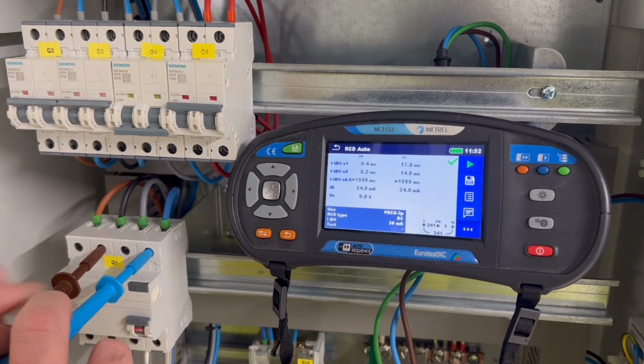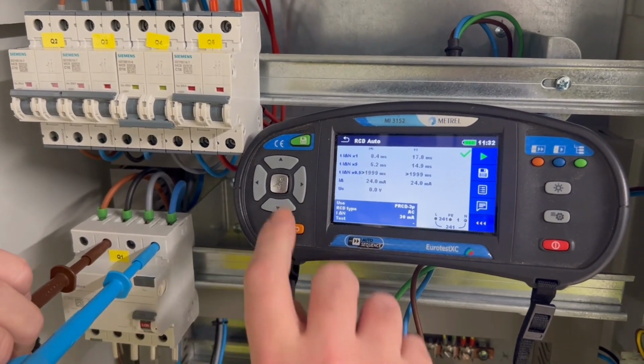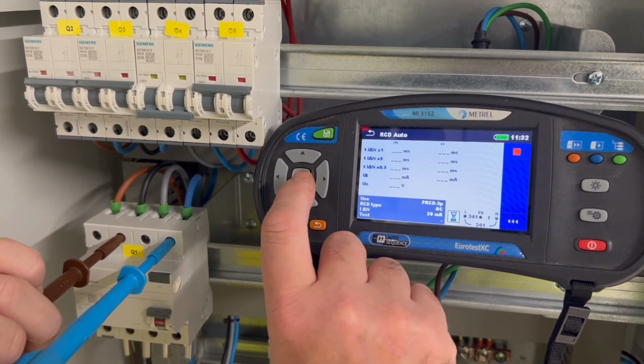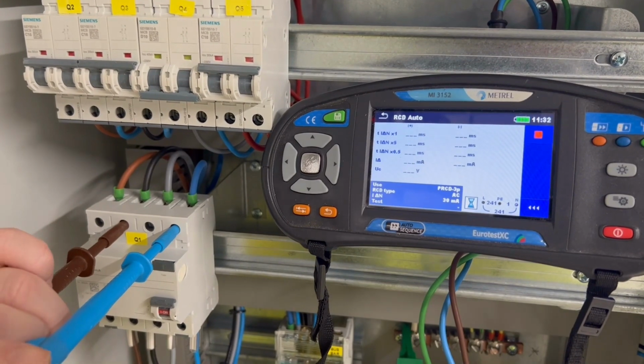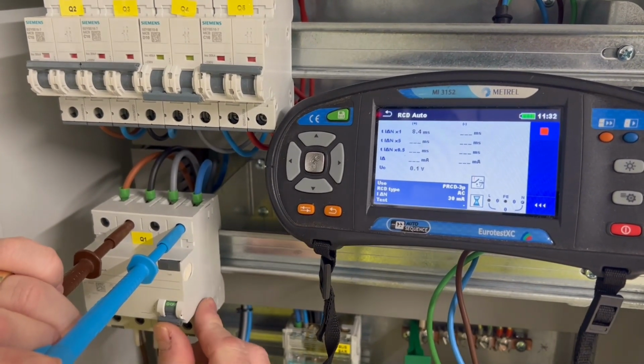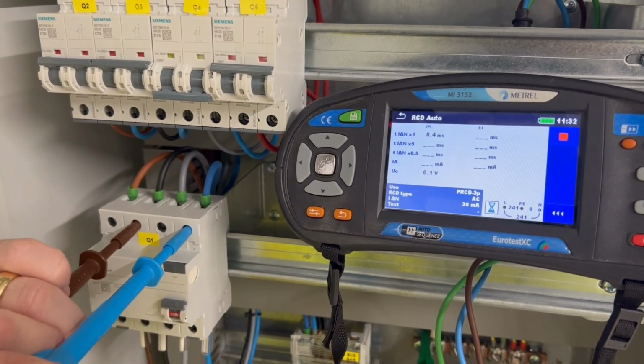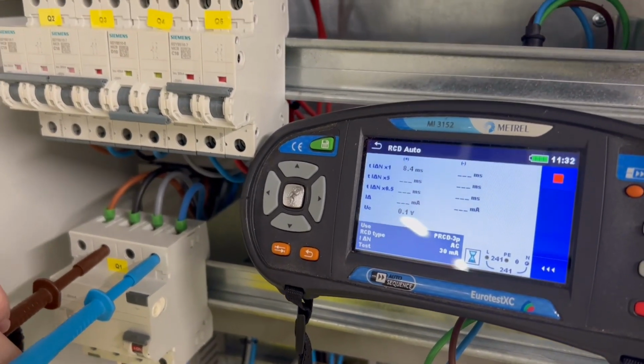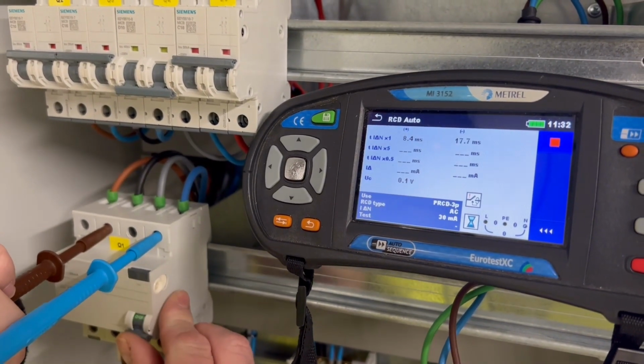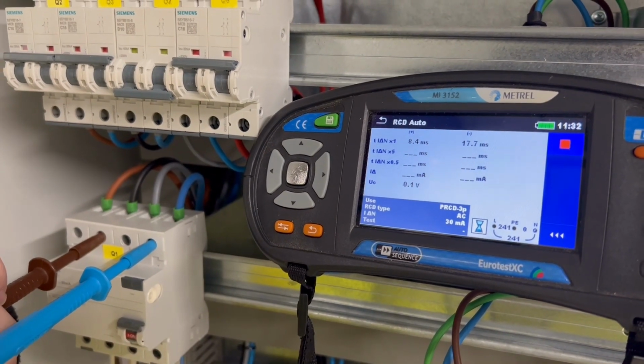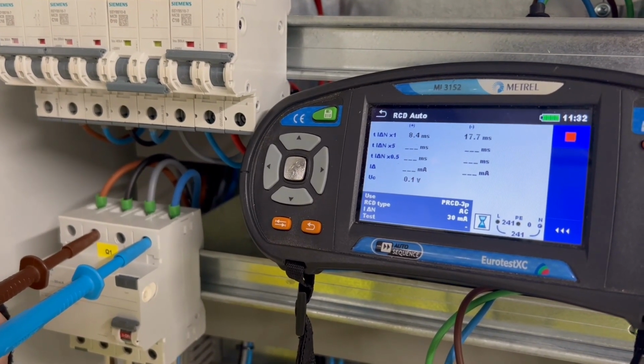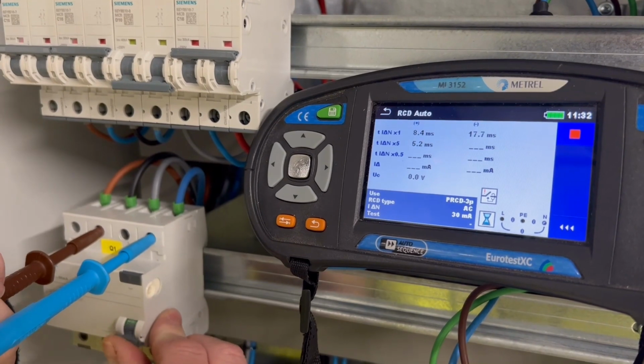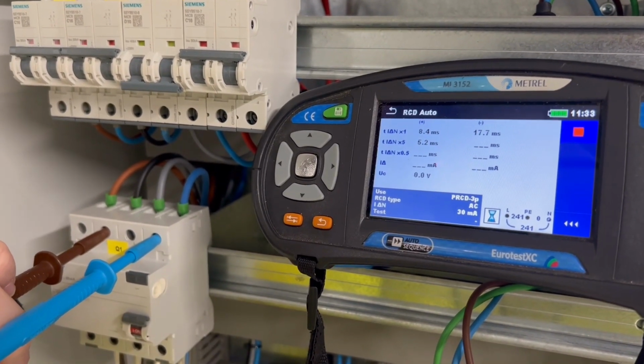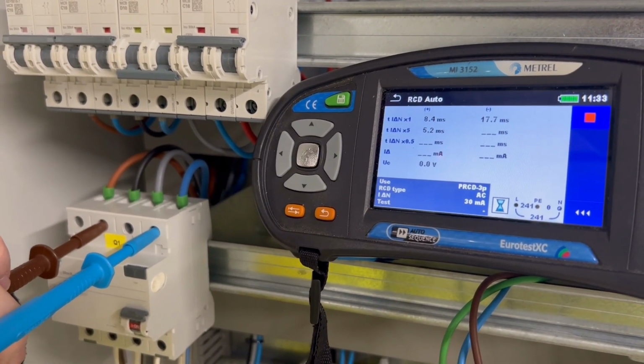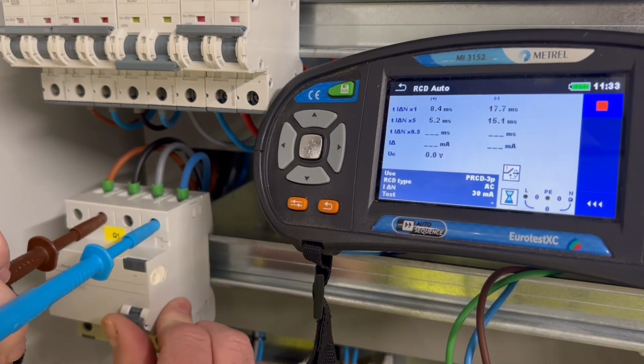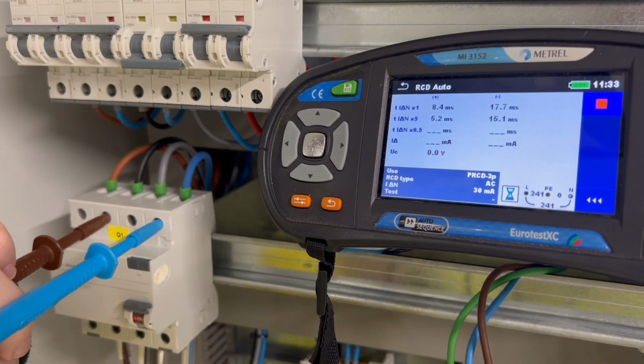We've got the earth connection to the earth bar, neutral, and we're testing on L2. We start the sequence off. The first sequence test is at times 1, so that's 30 milliamps on the positive cycle, and the unit trips out. It gives you an indication on the screen. That's 8.4 milliseconds, and the negative cycle is 17.7. Now we test at times 5, which is 150 milliamps, trip time of 5.2 milliseconds, and on the negative cycle we have a test time of 15.1.